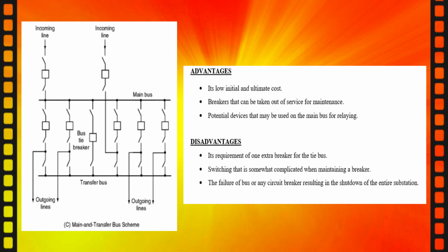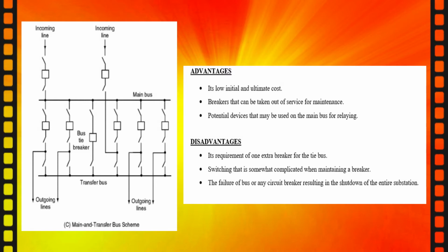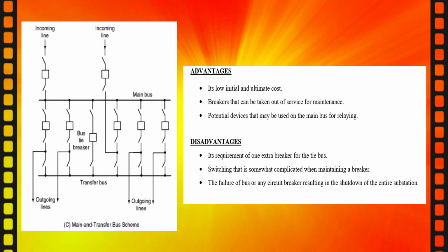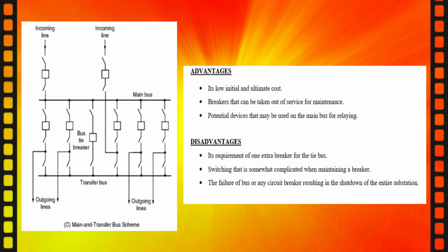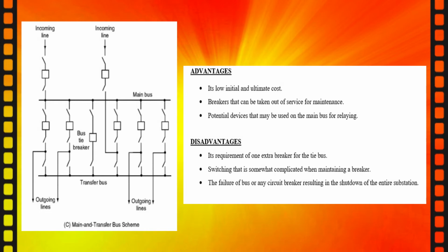Okay, for the disadvantage, it requires one extra breaker for the tie bus. Second, switching is somewhat complicated when maintaining a breaker. Then the failure of a bus or any circuit breaker results in the shutdown of the entire substation.